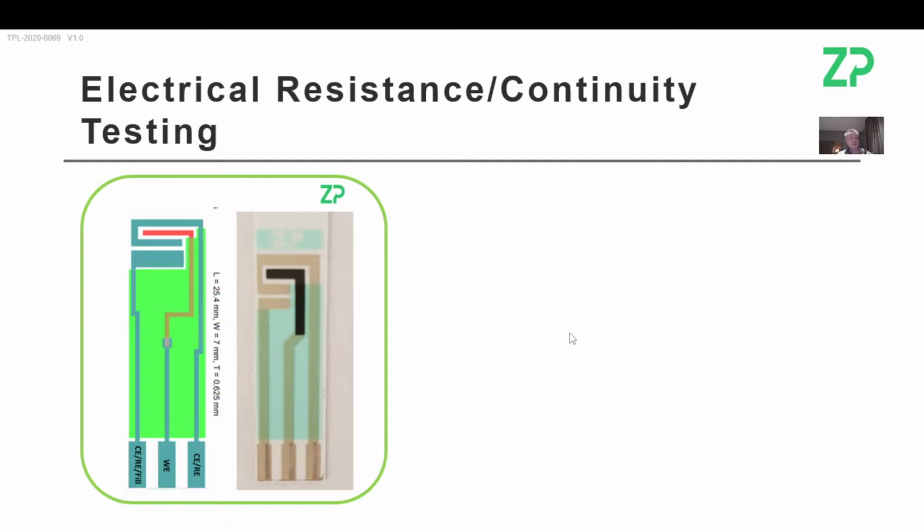When it comes to electrical testing, I mean, it's one of the easiest things to do. Everyone does it. What they don't tell you is it's a surrogate for doing other testing. It sort of works. So we'll test along these conductive tracks, make sure that they're within some sort of specification, so it's easy to do, so people do it. It's easy to automate. You can just come down with a reader, a bunch of what are called pogo pins or bed of nails, and make electrical contact and read them.